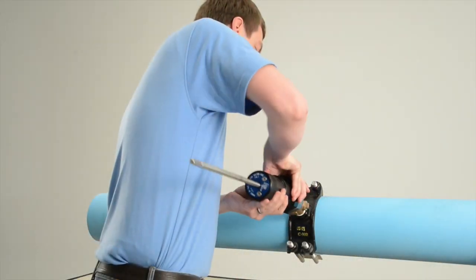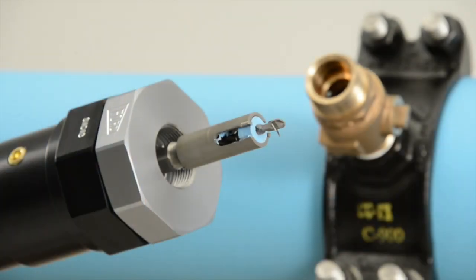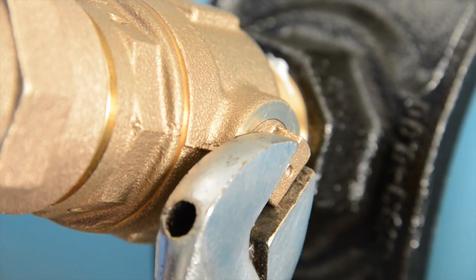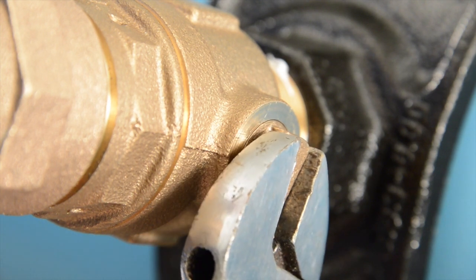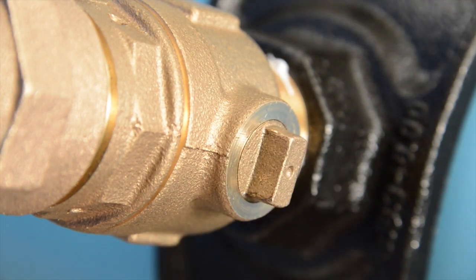Close the valve and remove the SimTap from the valve. Slowly open the valve to flush any chips or debris from the inlet of the valve. Close the valve and you are ready to attach the service line.